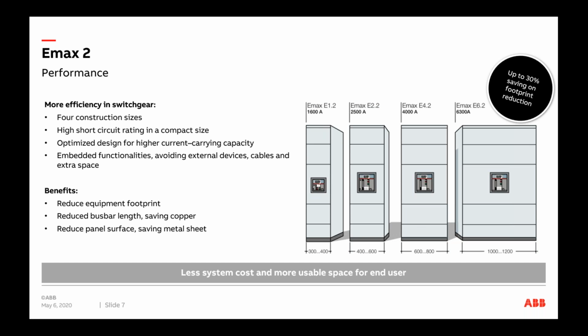We're talking about 4 construction sizes. So the E1.2, which is up to 1600 amps, can be fit onto a 400 mil wide tier. The E2.2 can be either a 400 or can go up to 600. Now the 400 would be limited to a 3-pole circuit breaker, and the E4.2 goes from 600 to 800, and then the largest one needs at least a 1000 mil wide switchboard to fit into. So this is how it's designed to try and not only look at the product and functionality, but also where it fits as a part of the system, to make it easy for the system to be designed and, let's say, flexible enough to fit into any sort of situation in a switch room while complying with installation and service rules that we have in the country.